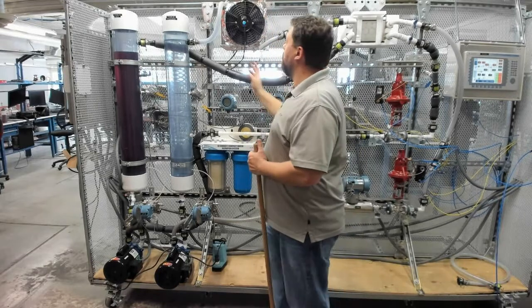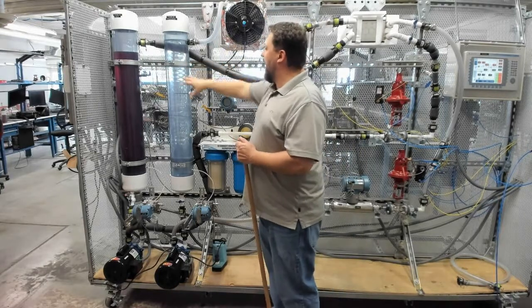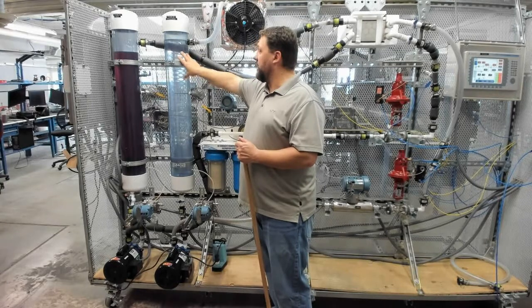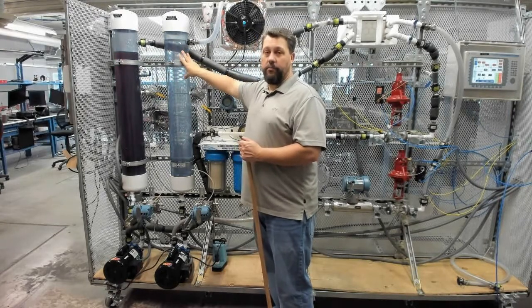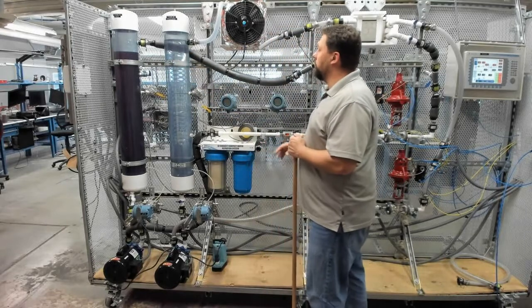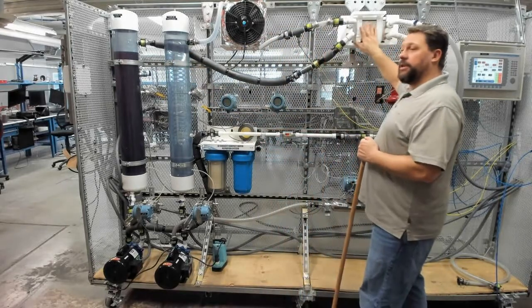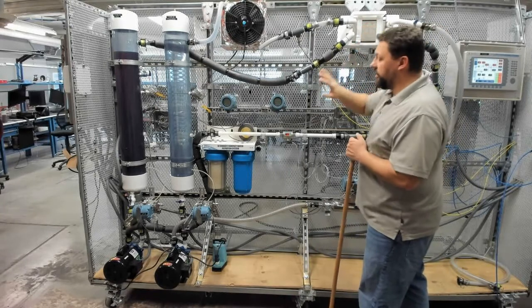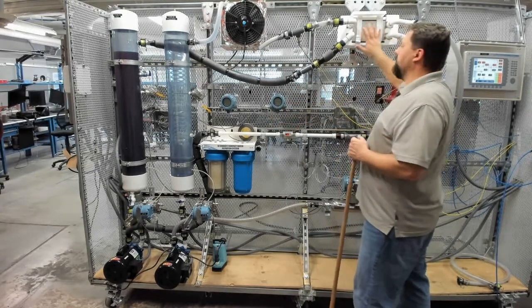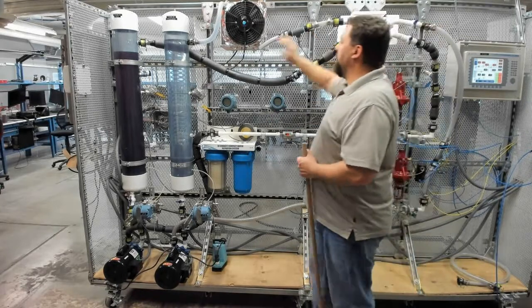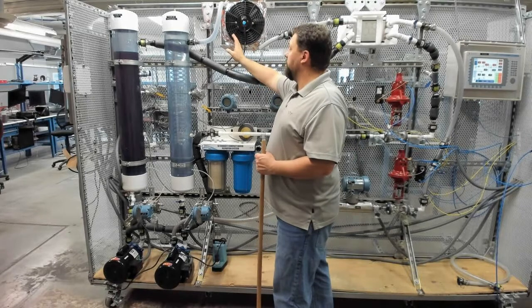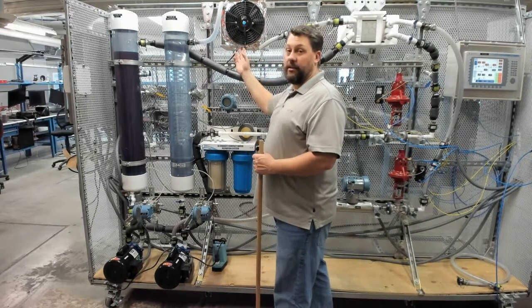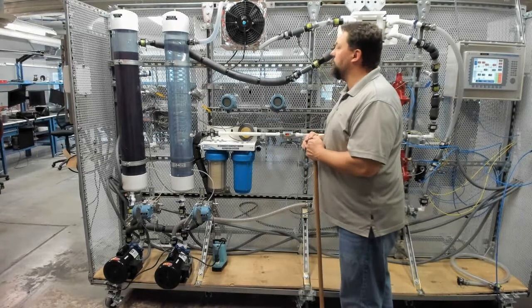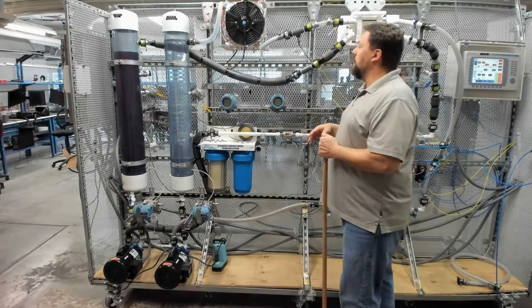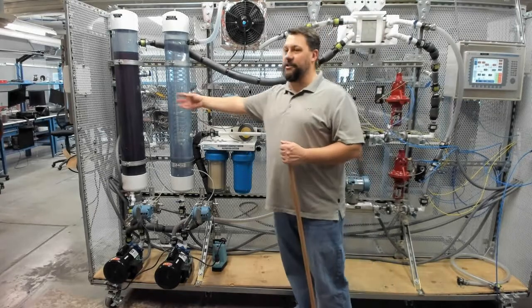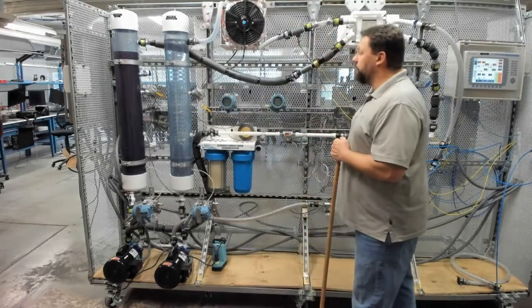Like I mentioned before, if we just continually added heat into this tank, it would get pretty warm pretty quickly and isn't very useful to us. So we're going to have a liquid to liquid heat exchanger here. So we're taking the thermal energy from the heat transfer fluid and injecting it into our process fluid. And then this is a liquid to air heat exchanger where we're extracting. So it seems counterproductive, but on a training skid, that's what you have to do. Otherwise, we'd always be trying to add ice or something in here to keep that temperature from going up.